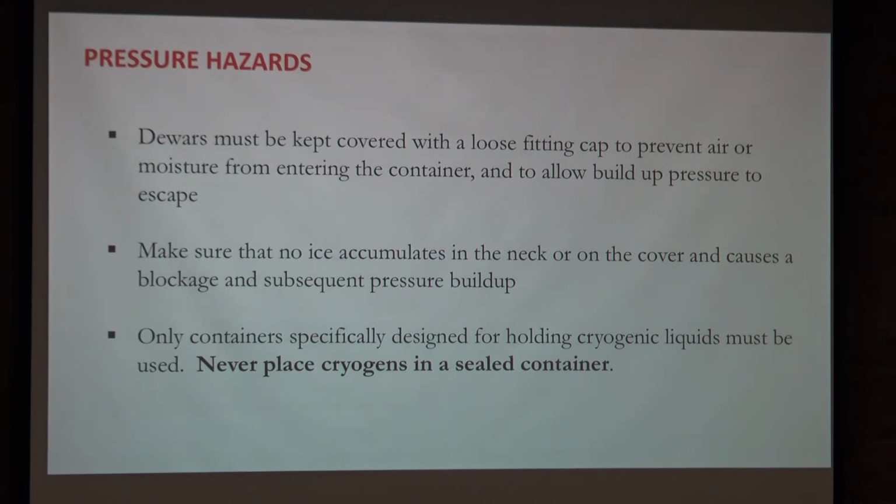You want to keep the neck of your Dewars always free from ice or any other gases that can freeze and cause blockage, and that blockage could then block the gas from escaping and lead to a consequential build-up of pressure. Basically, only use proper containers that are actually designed for keeping cryogenic liquids. Never place cryogens in a sealed container that does not provide any means of escape.